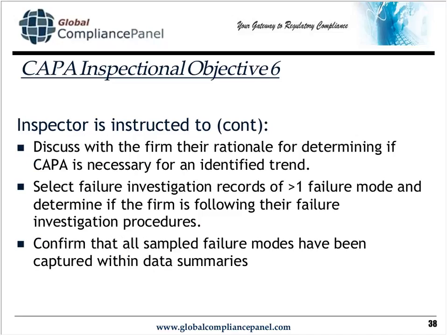The inspector is further going to discuss how you determine whether CAPA is necessary. And again, if you have this in your procedure, this discussion is moot. And the inspector is then going to look at failure investigation records of more than one failure mode. One isn't sufficient to determine any sort of trend. Well, maybe two isn't either, but this is what the guidance document says. And they're going to make sure, as I said, you're following your own failure investigation procedures.